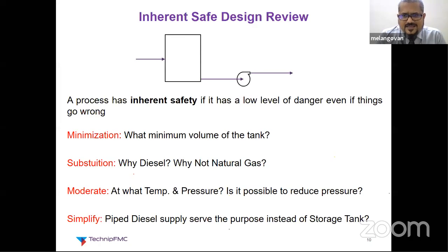This diesel tank can be sized to store diesel for 1 day of consumption, or 1 week, or 1 month, or 1 year. There is no limit to the capacity of the tank, but the risk for each case is different. For 1 day, for example, it is 100 liters, and for 1 week it will be 700 liters. If a leak happens, the consequence in the two cases will be different. In the first case, at worst, we may have a loss of containment of 100 liters of diesel, but in the second case, we have a loss of containment of 700 liters of diesel. So we need to agree on the minimum size of diesel tank that satisfies the end client's requirements.